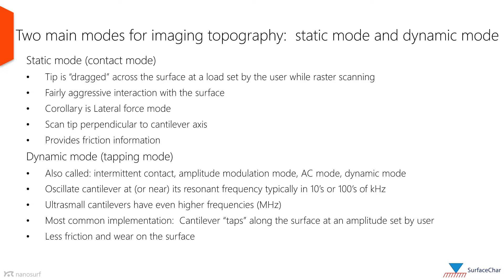In dynamic mode, which also has other names like intermittent contact or AC mode, the cantilever is oscillated at or near its resonance frequency, typically in the tens to hundreds of kilohertz, though it can be higher for small cantilevers. The oscillating cantilever taps along the surface at a set amplitude, virtually eliminating any lateral force and thus significantly reducing wear of both the tip and the sample.